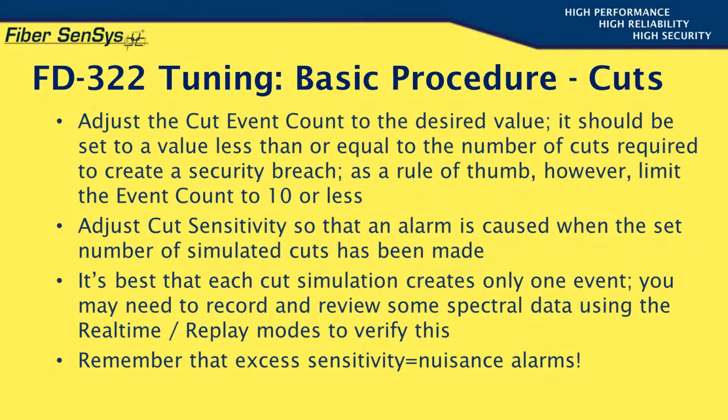Now let's move on to cut intrusions. The first step is to set the cut event count to the desired value. It should be set less than or equal to the number of cuts required to create a security breach. It's a good idea to keep the count to 10 or less, however.